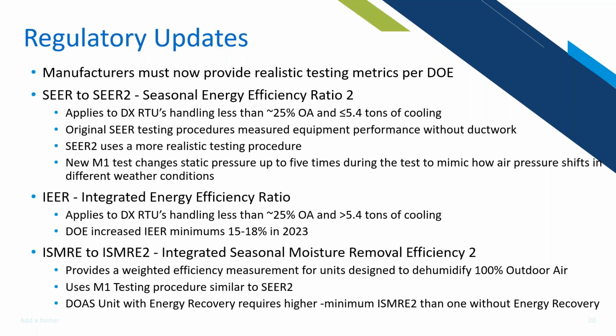Now, ironically, they did not make an IEER2. They just increased IEER, the integrated energy efficiency ratio, by 15 to 18% in 2023. That applies to DX RTUs handling less than 25% outside air and greater than 5.4 tons of cooling. But what's going to be more relevant to what we sell at Buckley is the ISMRE, the integrated seasonal moisture removal efficiency, which again has been tested with the M1 testing procedure. It provides a weighted efficiency to measure units designed for 100% outside air and the dehumidification associated with that.